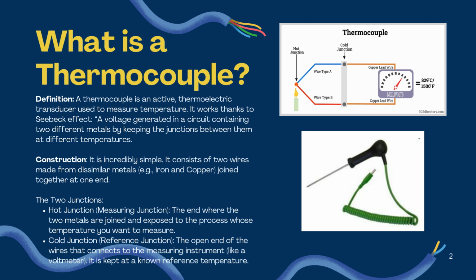The hot junction is where the ends of the two metals are joined and exposed to the process whose temperature you want to measure. As for the cold junction, it is the open end of the wires that connects to the measuring instrument, like a voltmeter. It is kept at a known reference temperature. On the right side, we can see the diagram of the thermocouple, which has the hot junction and cold junction, and it is connected to a voltmeter. And below is the picture in real life of a thermocouple.